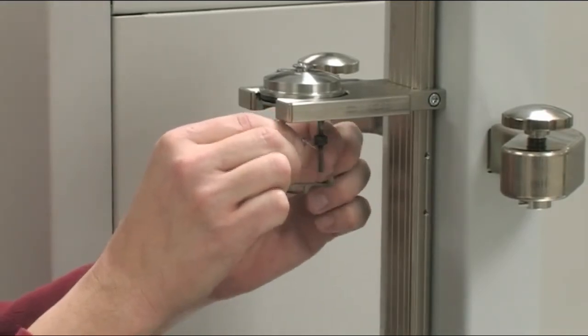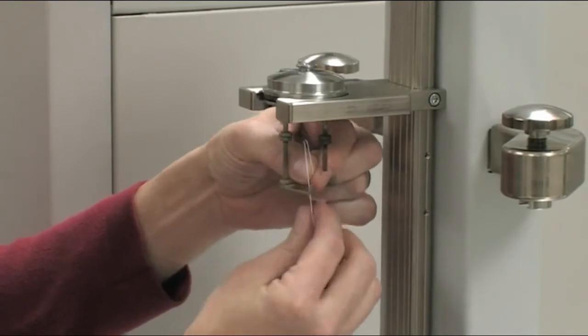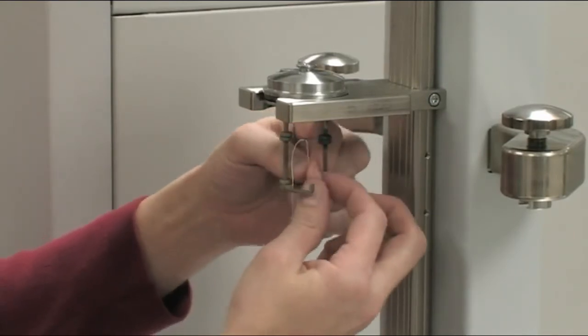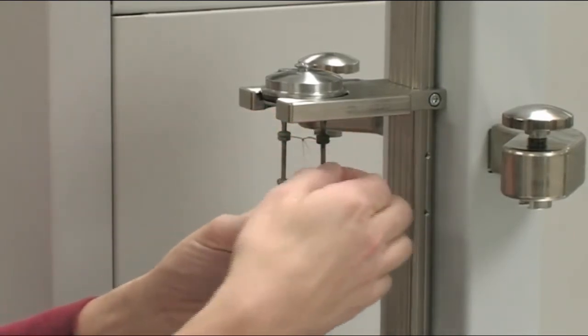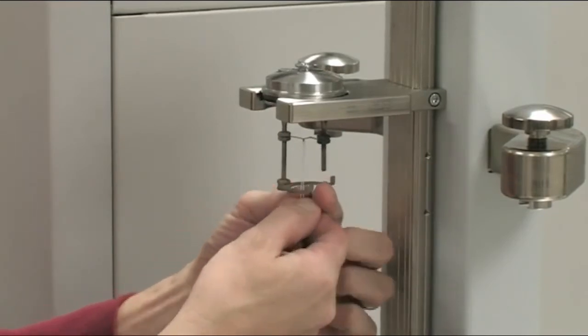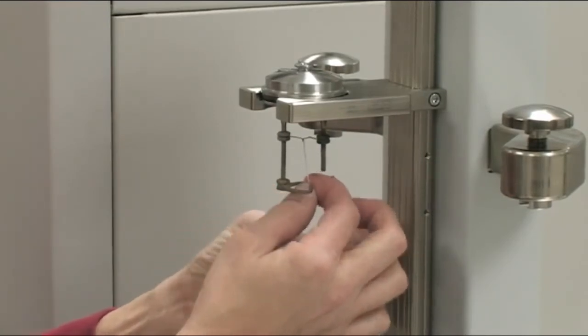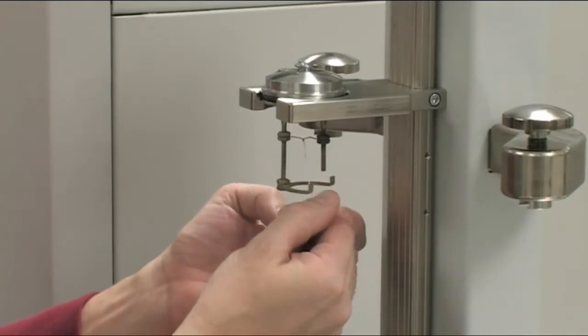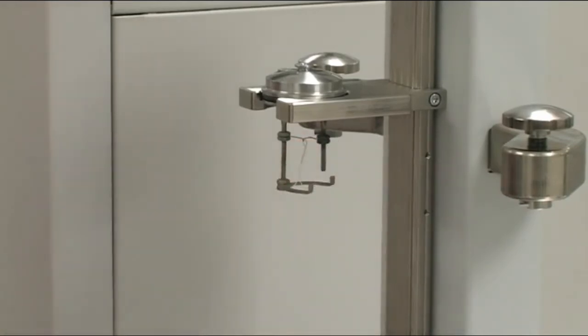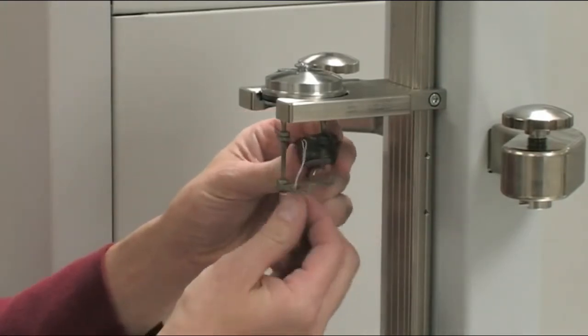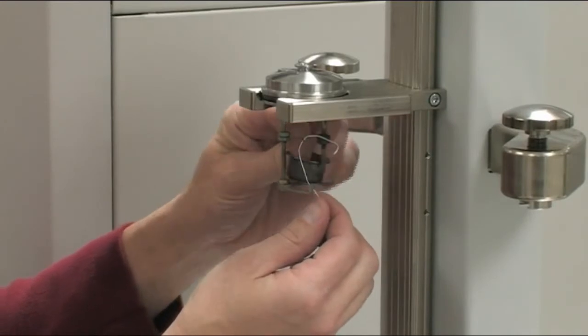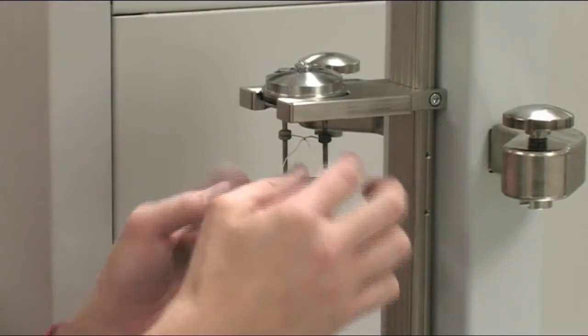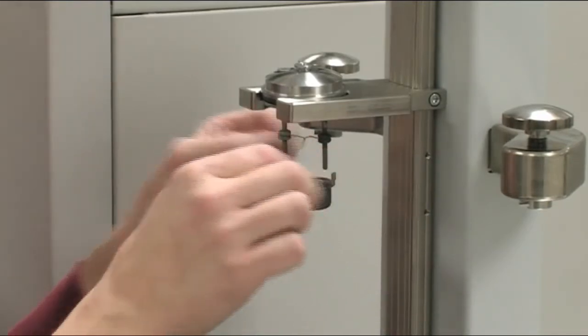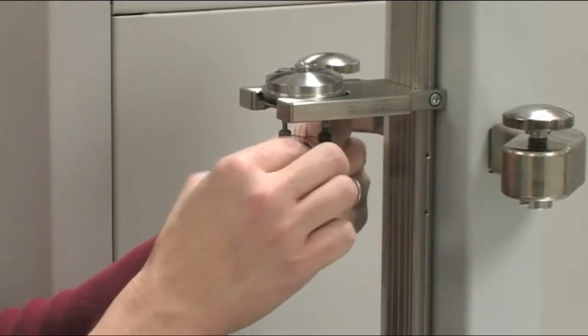What you do is you take the igniter string, hook it through the loop, pull it down, and give it a few twists. This attaches the ignition string to the wire. What you want to do next is you want to put the sample capsule in place. Take the igniter string and make sure the sample is placed on top of the igniter string.